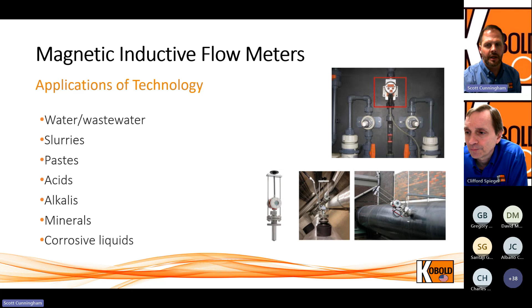Similarly, with ultrasonic, we do have some upstream and downstream straight pipe run requirements for best practice. For the MIM it's 3x upstream and 2x downstream—a little less than ultrasonic, but again those are best practices. These are relatively small meters, so worst case, with a 2-inch one, that's 6 and 4 inches. It's not much for this type of meter.